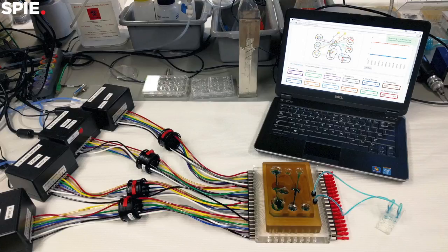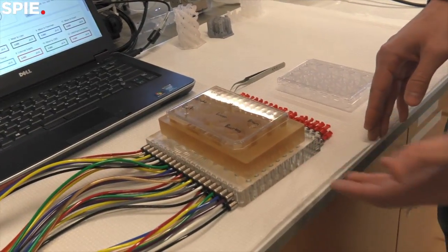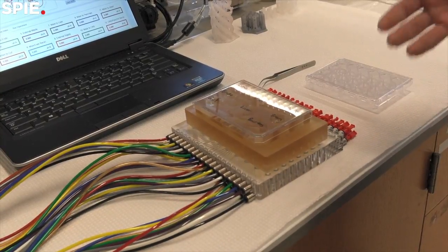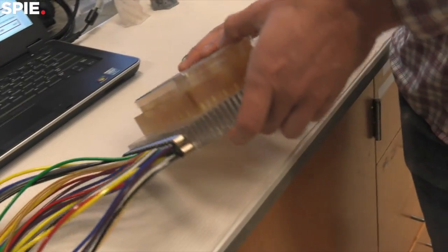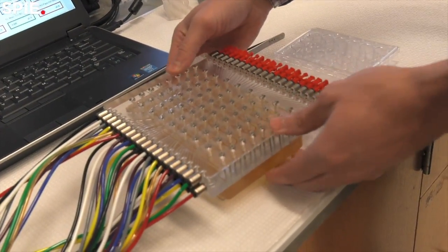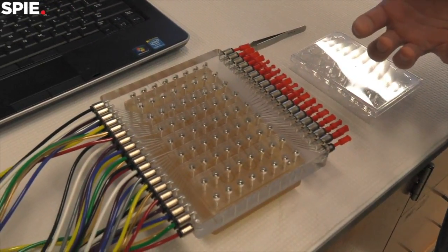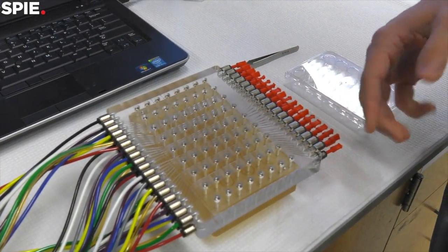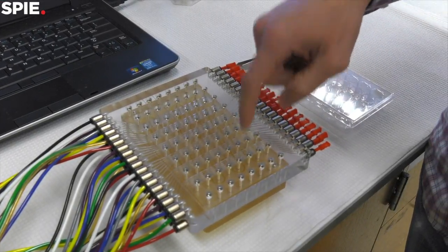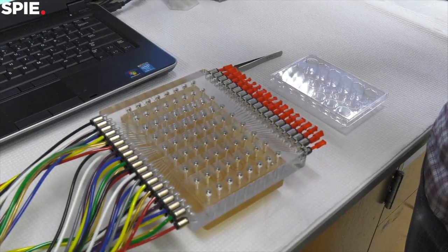So, the way this system works, we have a three-layer hardware platform. The top layer holds the fluid and maintains sterility. The bottom layer is an acrylic manifold that delivers pressurized air and vacuum to the pump locations under the plate. Beneath the plate and sandwiched between the plates is an elastic membrane that seals the fluid channels and also provides the actuation layer for the pump.